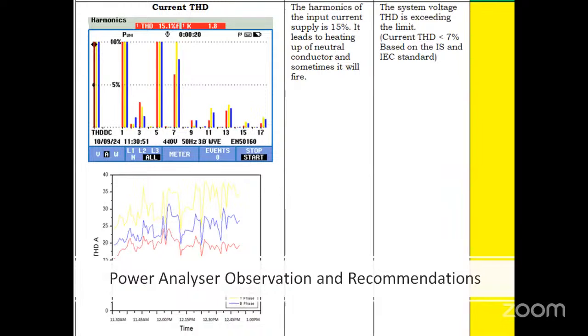This is the harmonic data from the power analyzer. In the waveforms, we can see the harmonics - the current harmonics is 15%, whereas the recommended value should be less than 7%. For such cases, we give recommendations for going for filters.